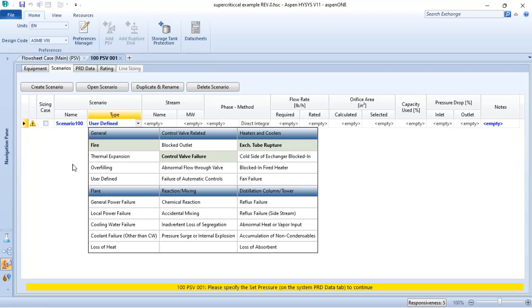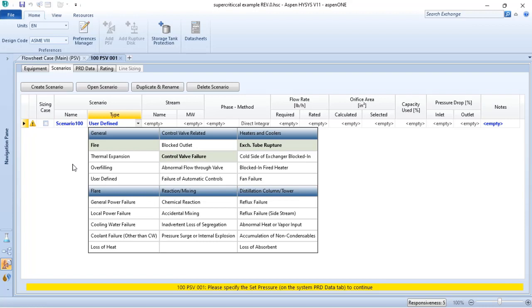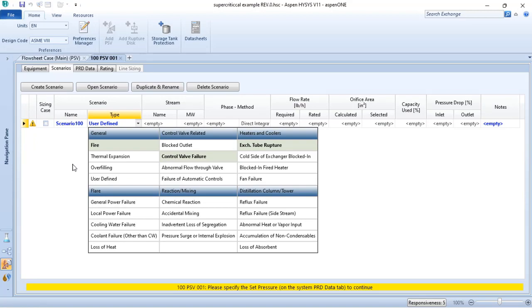Imagine that you need to compress a fluid to a process and in the aftercooler it is a shell and tube heat exchanger and you use a cooling water system with a pressure around 3.5 bar G. If for any reason the heat exchanger tube ruptures or if you get a hole in the tube because of corrosion, for instance, you need to verify what happens when the fluid at high pressure goes to the side of the lower pressure of your system. So these are examples of scenarios for pressure relief device calculations.